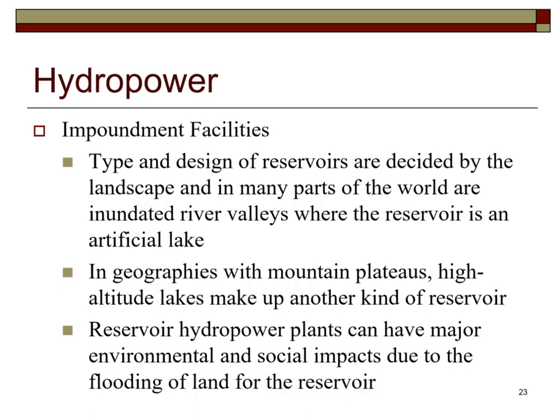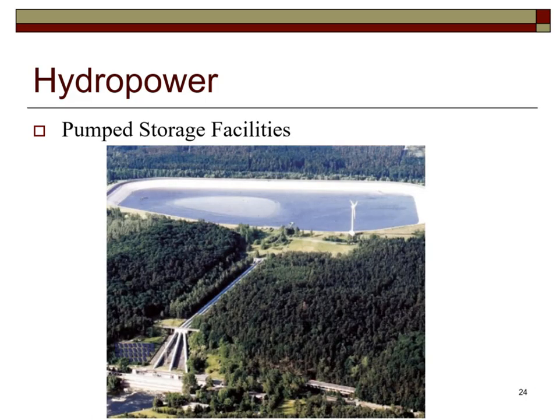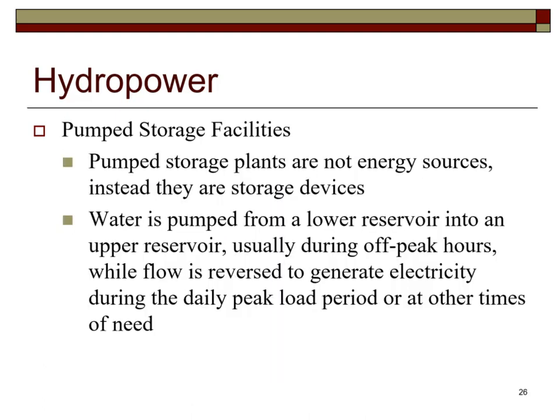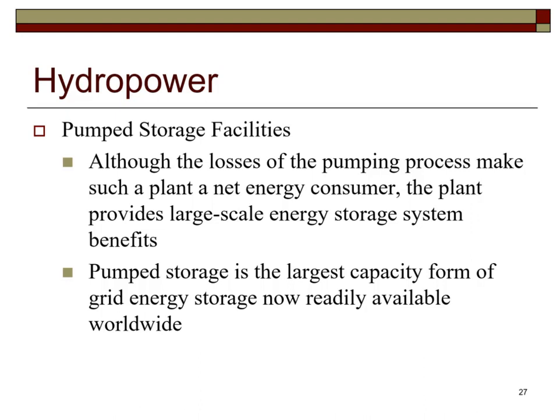Reservoir hydropower plants can have major environmental and social impacts due to the flooding of land. Pumped storage plants are not energy sources—they are storage devices. Water is pumped from a lower reservoir into an upper reservoir, usually during off-peak hours, and flow is reversed to generate electricity during peak load periods. Although the pumping process makes such a plant a net energy consumer, it provides large-scale energy storage benefits and is the largest capacity form of grid energy storage available worldwide.